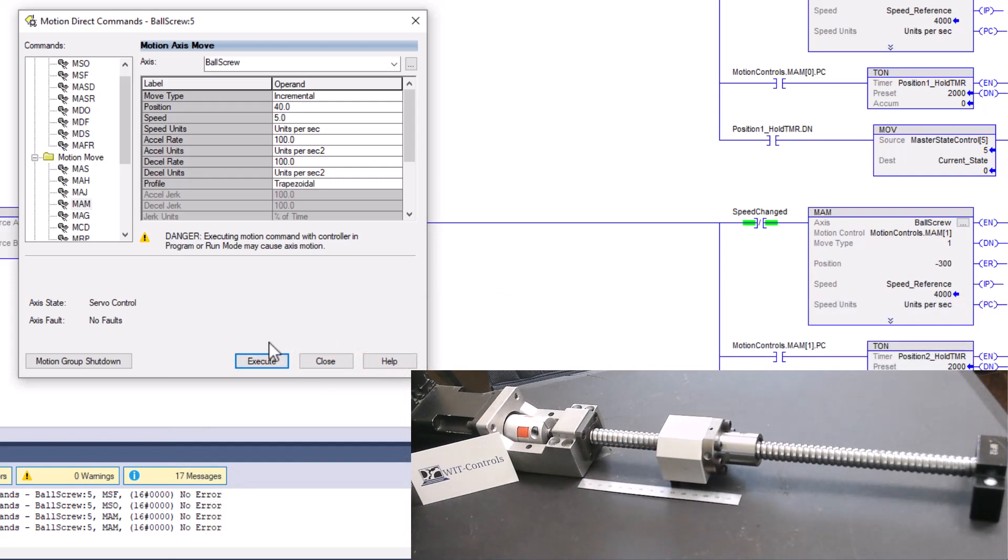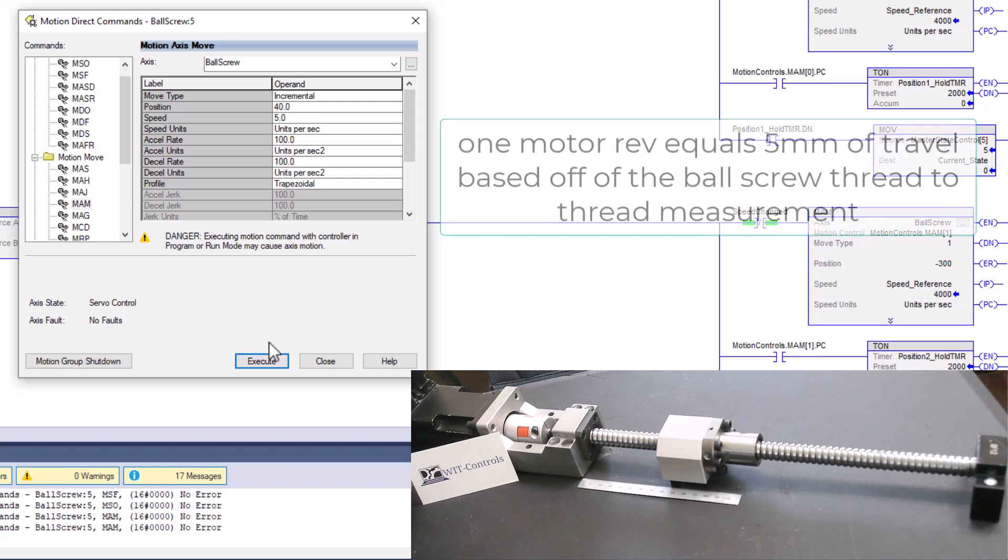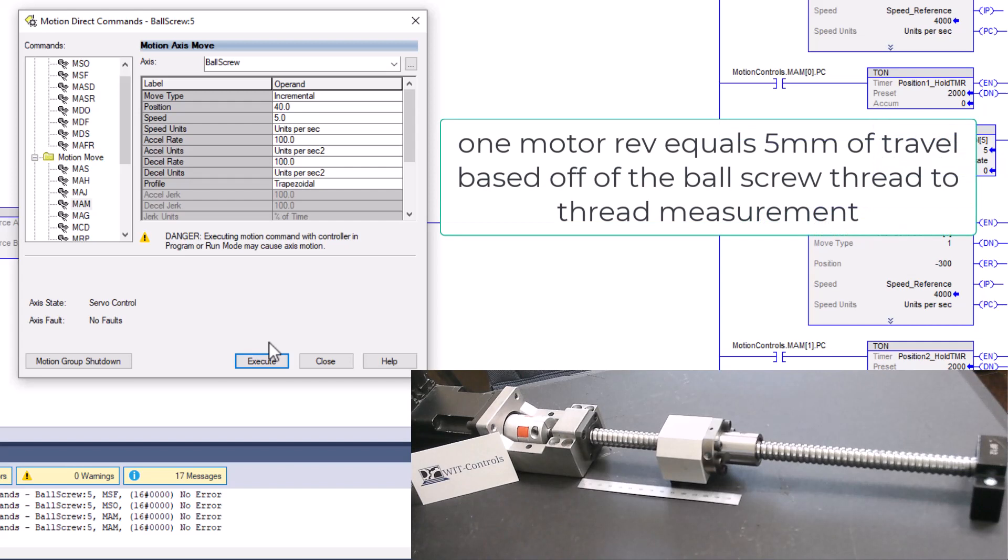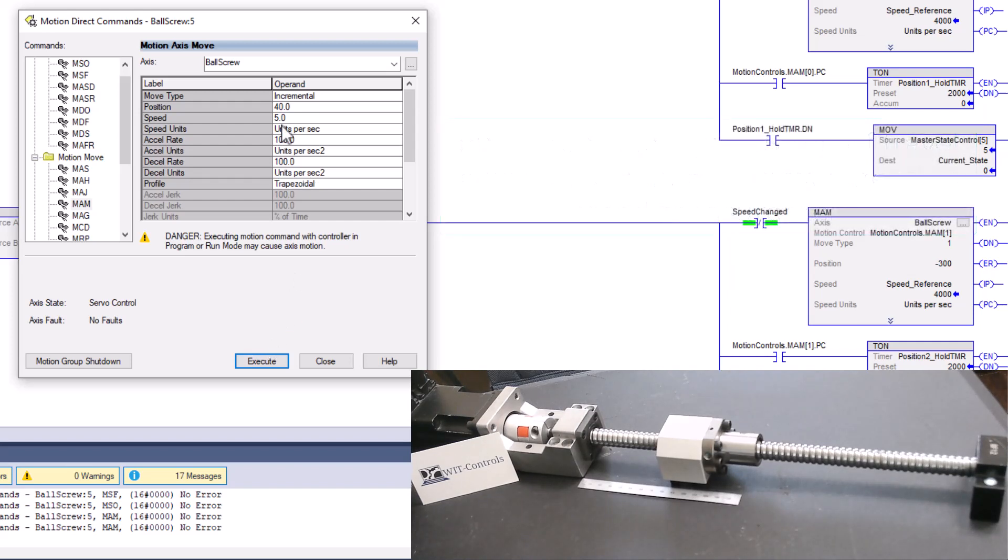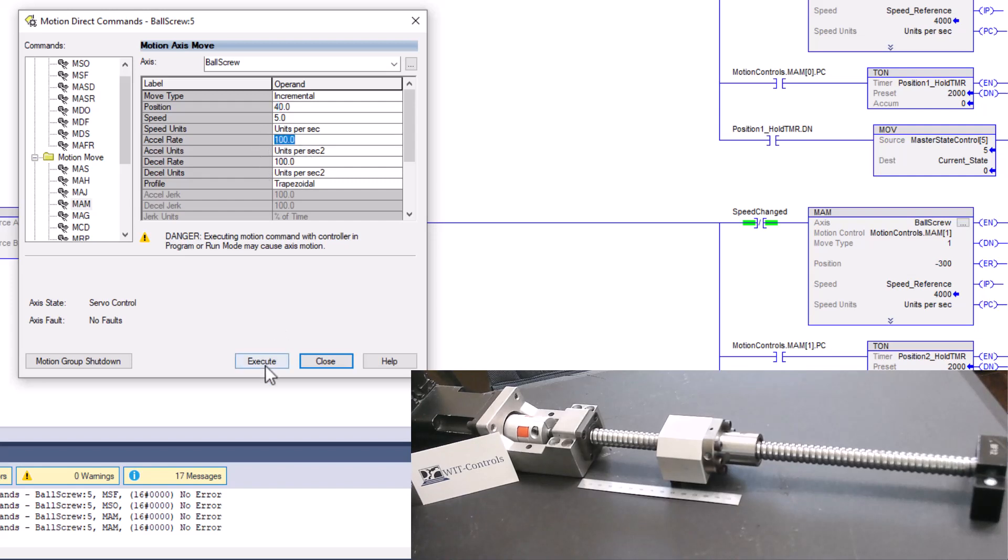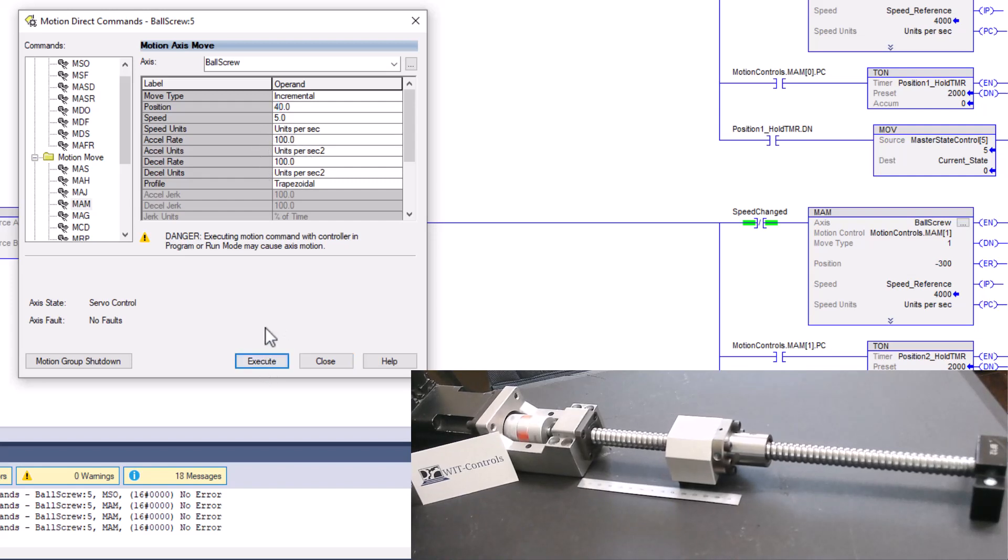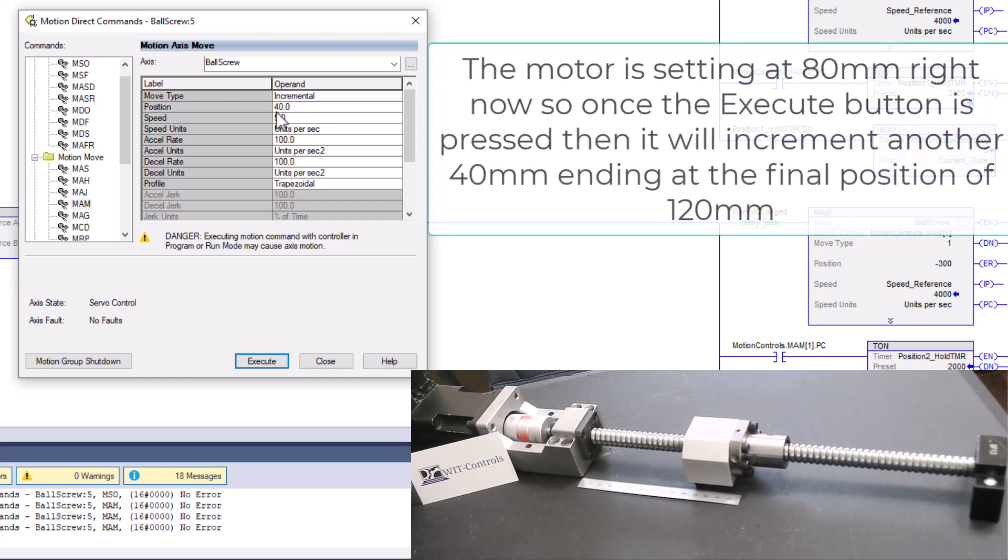Again, this is a very simple scenario because this is a motor directly connected to a ball screw. And that ball screw, just all you have to know is the conversion of that ball screw, which happens to be the measurement. So you measure from thread to thread, the center of the thread to thread, and that's your pitch. And that's how I got the pitch on this. So in this case, let's go ahead and do another move of 40. Now if you wanted to move it backwards, I'll show you how to do that as well.